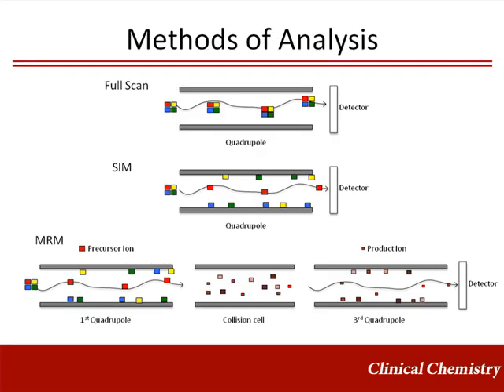For the linear quadrupole, full scanning is helpful in situations where the analytes of interest have yet to be determined. The resultant data is complex, but the potential for discovering unknown components exists. The lack of specificity reduces the utility of this method for routine clinical testing. Importantly, with the use of a tandem mass spectrometer, scanning can be done in the first and third quadrupole.